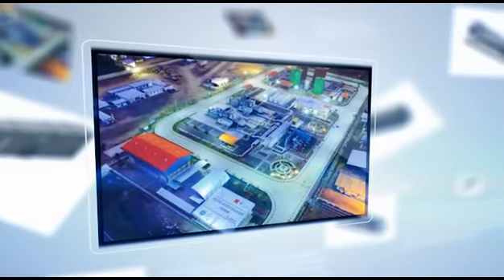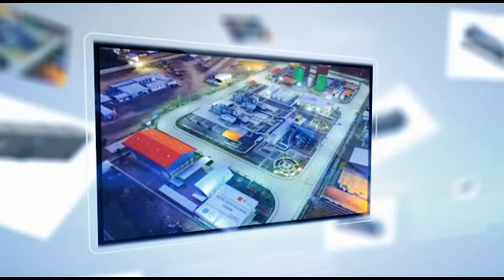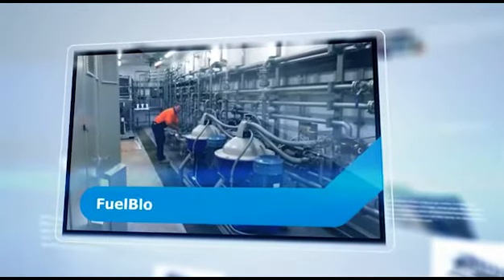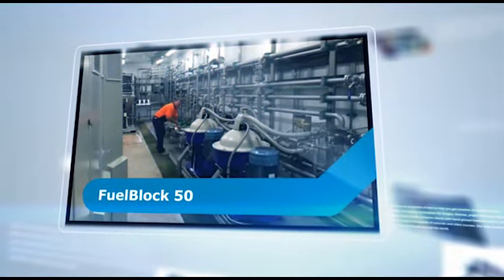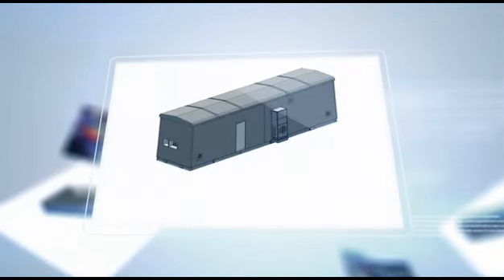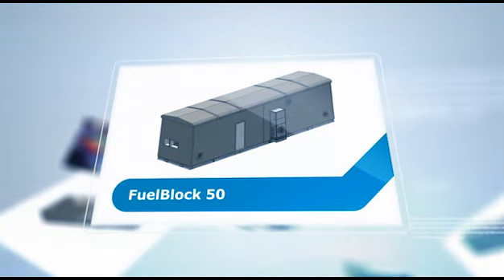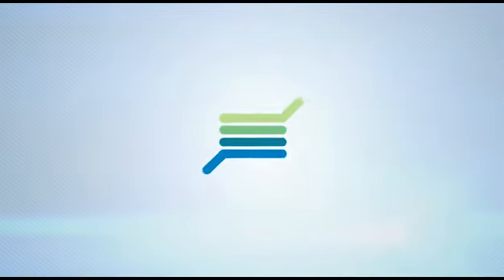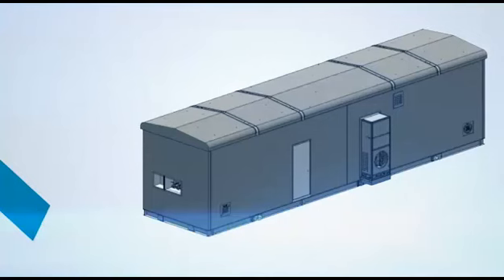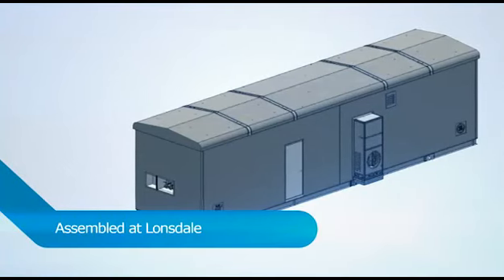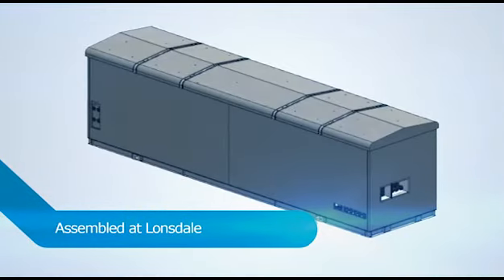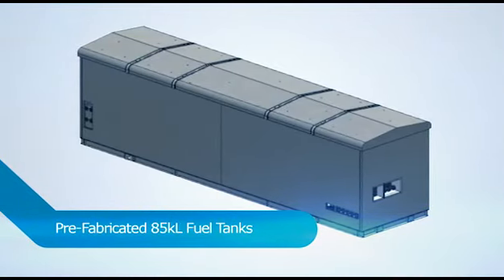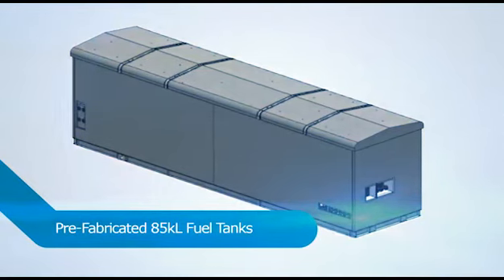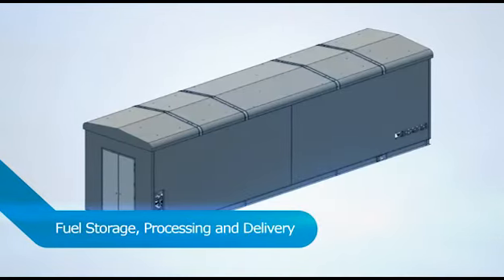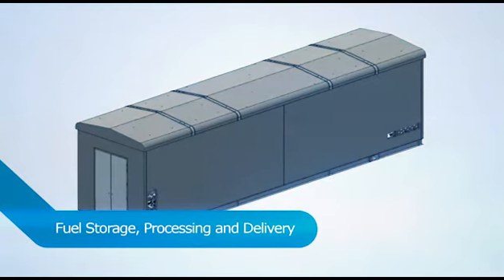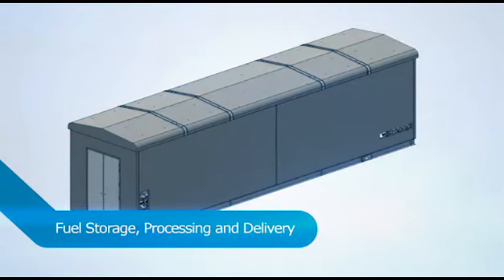The Fuelblock 50 is a liquid-fueled processing and delivery system capable of supplying two 25 megawatt aero-derivative gas turbine generators. The Fuelblock 50 can also be configured to supply a single 50 megawatt turbine generator. The module and all equipment are assembled at Lonsdale and fully commissioned before shipping to site. Once at site, the Fuelblock 50 is connected to prefabricated 85 kilolitre fuel tanks to provide a fast, complete solution for liquid fuel storage, processing and delivery.